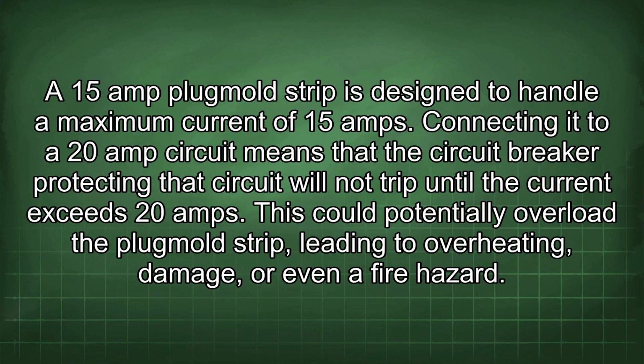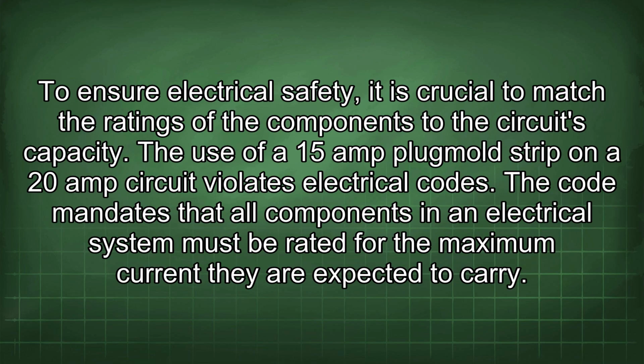A 15 amp Plugmold strip is designed to handle a maximum current of 15 amps. Connecting it to a 20 amp circuit means that the circuit breaker protecting that circuit will not trip until the current exceeds 20 amps. This could potentially overload the Plugmold strip, leading to overheating, damage, or even a fire hazard. To ensure electrical safety, it is crucial to match the ratings of the components to the circuit's capacity.